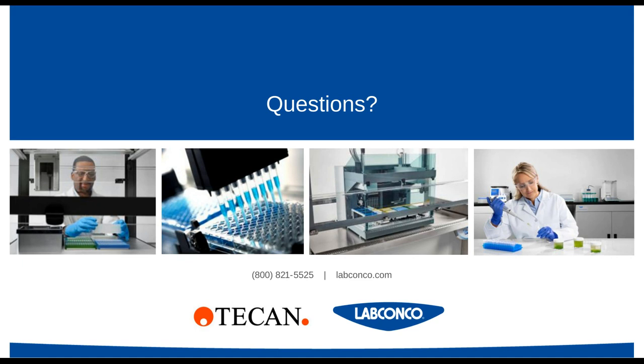And the next question is, we have a liquid handler that just barely fits inside our normal tissue culture hood. Is this safe to operate? Good question. If it just barely fits inside, as a manufacturer of biosafety cabinets with lots of experience testing such installations, it is difficult to make a black and white answer. So the best thing to do is to first consult your biosafety officer on site, involve your regular certification professional who's going to be testing the biosafety cabinet as well, and then also consult with the manufacturer of the biosafety cabinet and with the manufacturer of the instrument that's going to be placed inside.